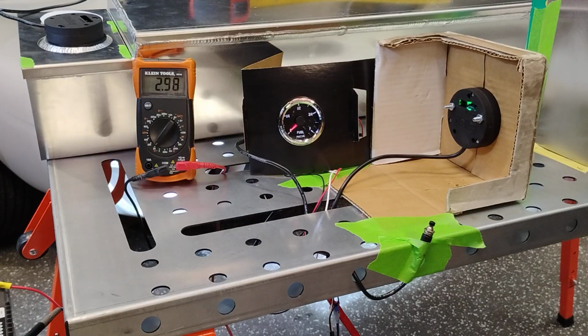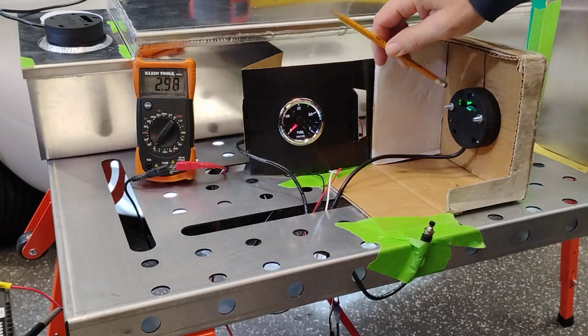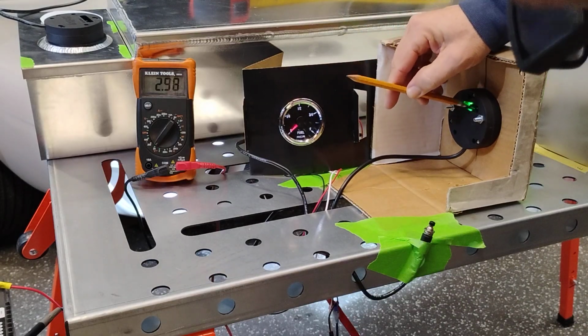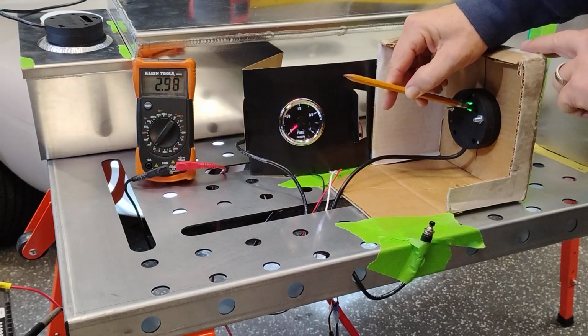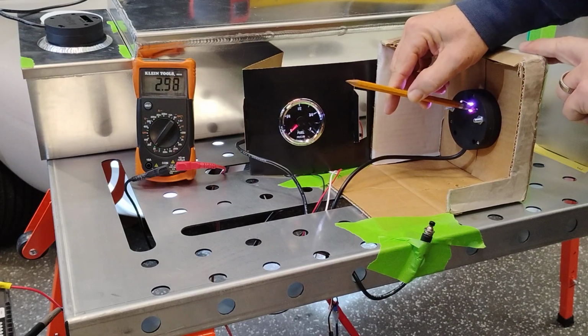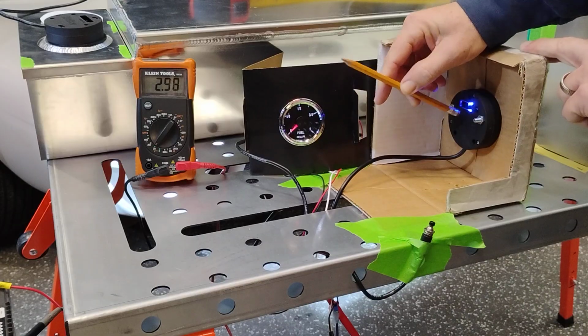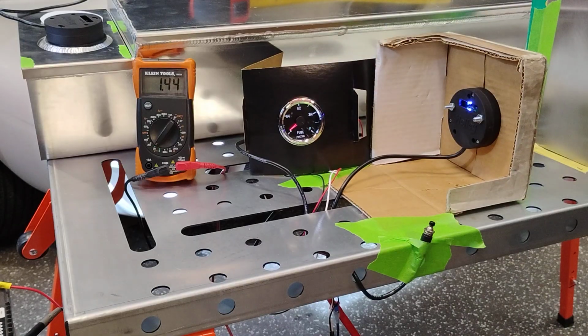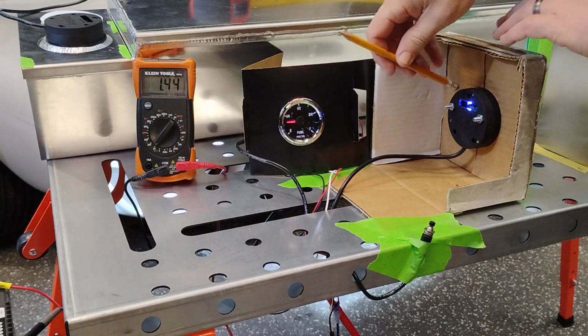Basically you're starting with the empty position, which you want to be at 2.69 volts. So you push and hold this button down, the P1 button, until the LED goes out, and then you'll see a solid blue light. Now you see the voltage has changed - that's what it's currently set at for the empty position. We want that voltage to read 2.69 volts, or at least as close as we can get.